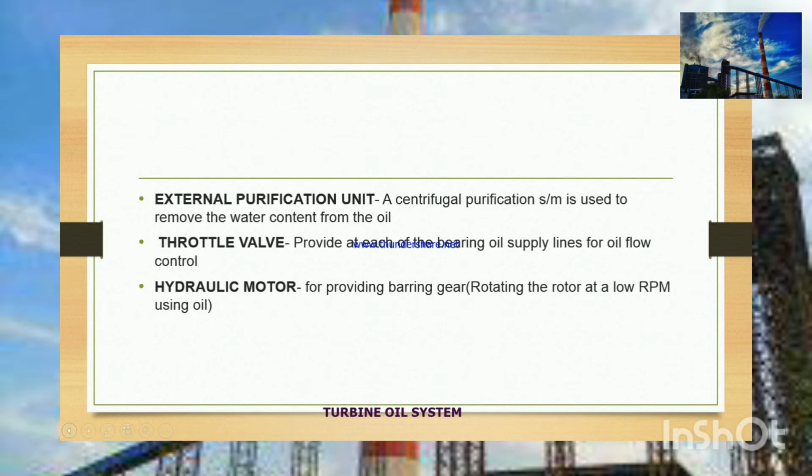For removing water content, we use an external purification unit. It works on the centrifugal principle. Then the next component is the throttle valve. There will be throttle valves at each individual supply line of bearing lubricating oil for controlling the lubricating oil supply pressure at each of the bearings.